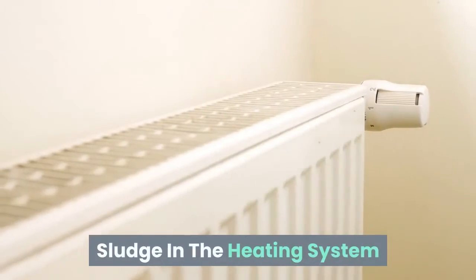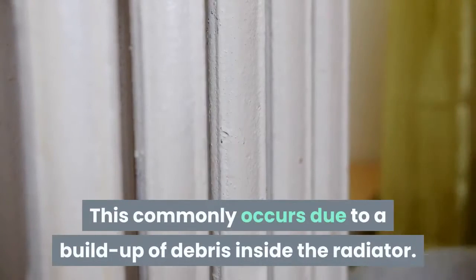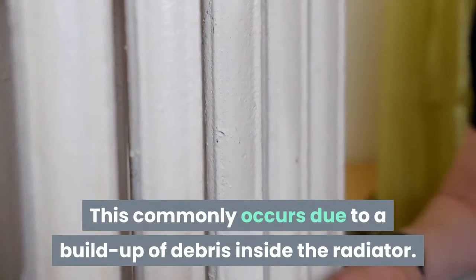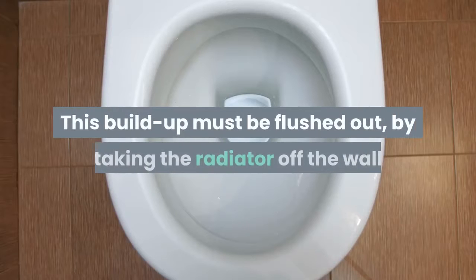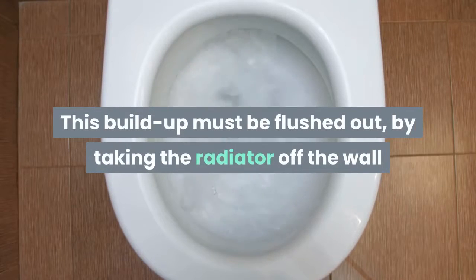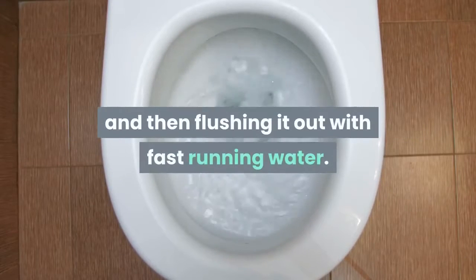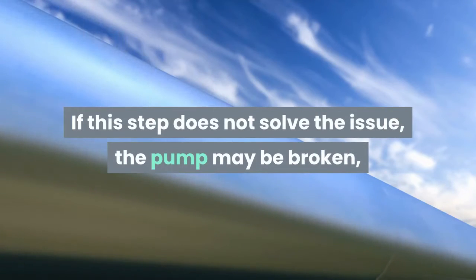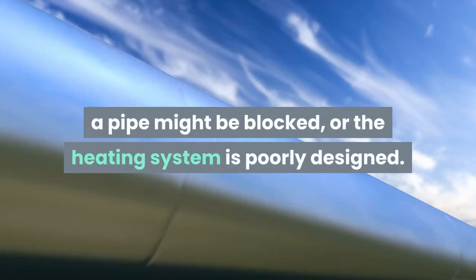Sludge in the heating system. This commonly occurs due to a buildup of debris inside the radiator. This buildup must be flushed out by taking the radiator off the wall and then flushing it out with fast-running water. If this step does not solve the issue, the pump may be broken, a pipe might be blocked, or the heating system is poorly designed.